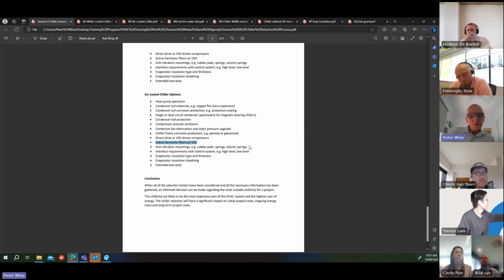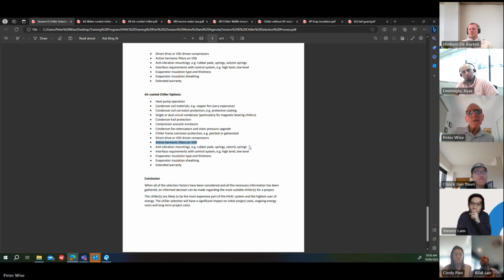We tested the chiller in the factory without springs, and a representative of the acoustic company came out with an accelerometer, which is used for measuring vibration, and they couldn't detect any vibration at all. So in the end, we were able to install a chiller without springs on a very vibration sensitive project. So that was quite impressive. I was surprised myself, but we found that out. The manufacturers were saying there's no vibration, and even some of the big centrifugal chillers, they'll put a coin on its side on the compressor, and the coin doesn't move. It's pretty impressive when you can do that. So vibration is minimal with these compressors.